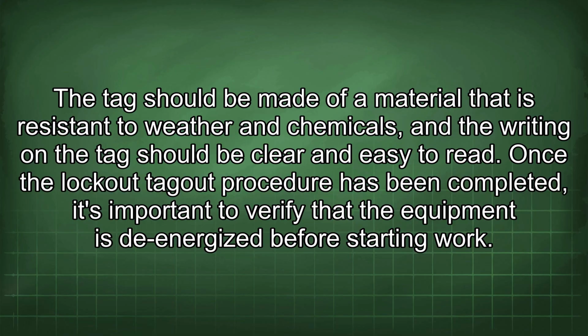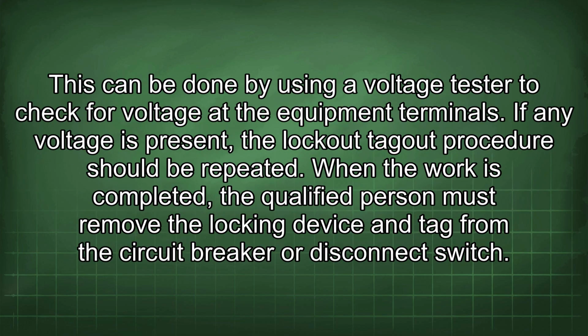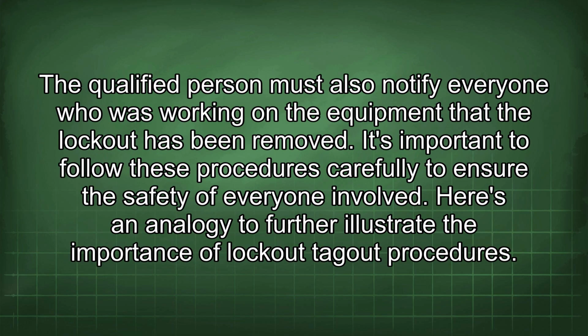Once the lockout tag-out procedure has been completed, it's important to verify that the equipment is de-energized before starting work. This can be done by using a voltage tester to check for voltage at the equipment terminals. If any voltage is present, the lockout tag-out procedure should be repeated. When the work is completed, the qualified person must remove the locking device and tag from the circuit breaker or disconnect switch. The qualified person must also notify everyone who was working on the equipment that the lockout has been removed. It's important to follow these procedures carefully to ensure the safety of everyone involved.